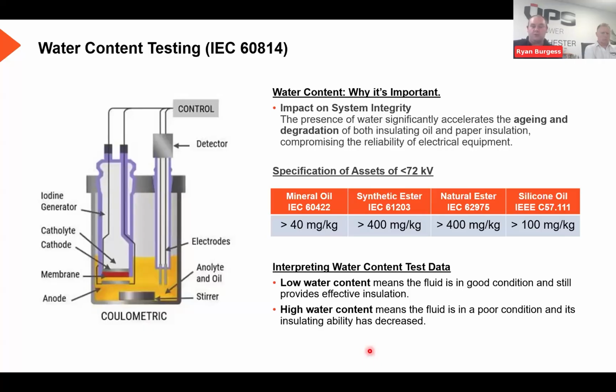So first of all, we'll look at water testing. So water testing is probably, of the fluid quality tests, the most critical test to understand. So it's important to understand how much water is present in a transformer, as the presence of water reduces the insulating properties of the oil, and it also speeds up the aging of the oil as the water increases.